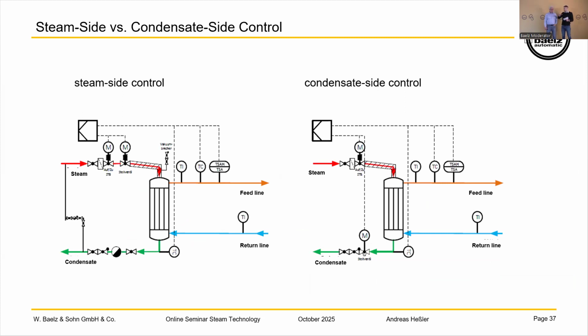There's no pressure because there's a layer where there's the difference, the Übergang. In English, the transition. Yeah, good. Thank you. Thanks from the technical boys here in the background. There's the transition from steam to condensate, and there will be no steam in the condensate line at the condensate side control. No, it's not needed. We also have temperature sensors to check the temperature of the condensate, to tell if the temperature is too high. If we have some steam, there is no issue. All right, thank you.